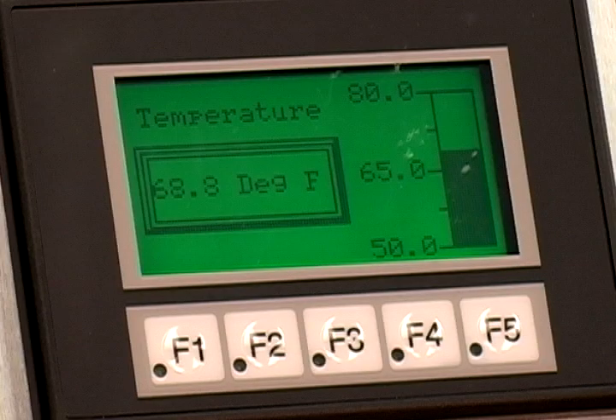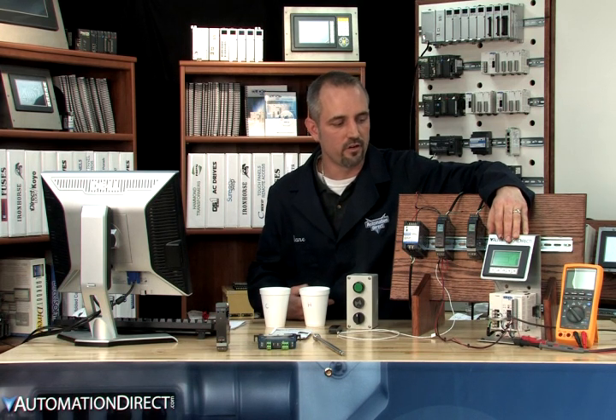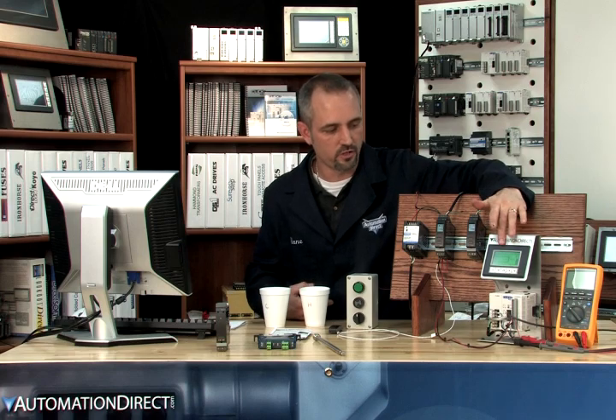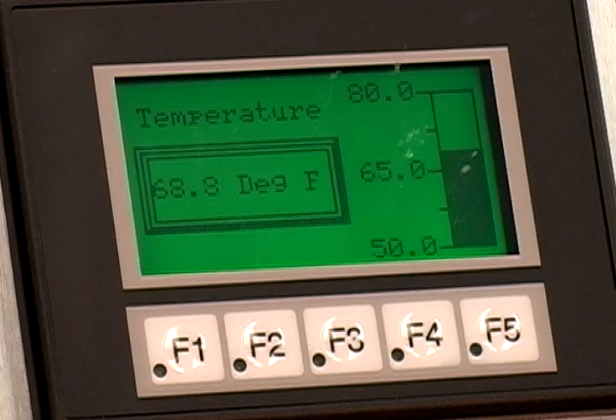We programmed the signal conditioner to close the relay contact when the temperature has reached 70 degrees Fahrenheit. When the contact closes, we apply power to our green indicator light. We also have a C-more Micro display panel connected and programmed here to display the temperatures. It can display converted ranges that may better suit your application versus just displaying raw data. What we have today is displaying the true temperature and also a temperature bar graph that displays from 50 to 80 degrees Fahrenheit.